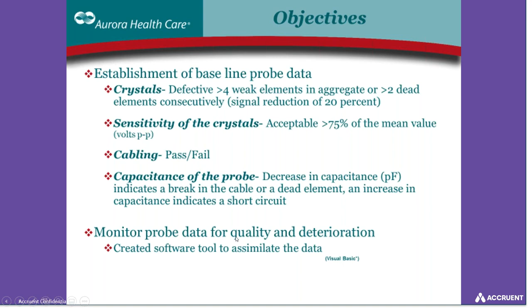So we set thresholds for greater than 4 weak elements, greater than 75% of the mean value, and sensitivity of the crystals, cabling, capacitance of the probe, monitoring probe data for quality and deterioration. And again, minimizing system downtime, being proactive rather than reactive, increasing the quality of the scans. I think everybody should understand that a sonographer makes all the difference in the world relative to the quality of the scans, and a lot of times these folks can make the most out of a less than stellar probe.